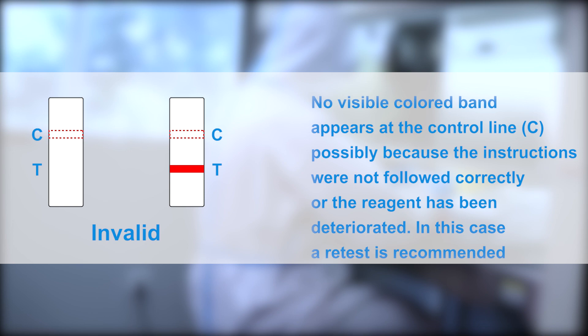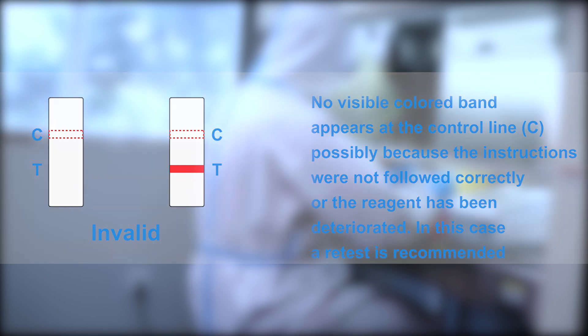Invalid result: No visible colored band appears at the control line, possibly because the instructions were not followed correctly or the reagent has been deteriorated. In this case, a retest is recommended.